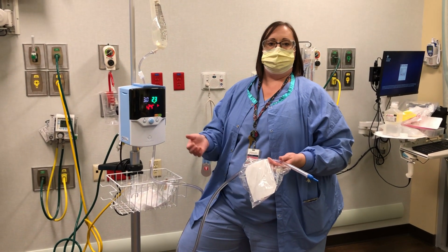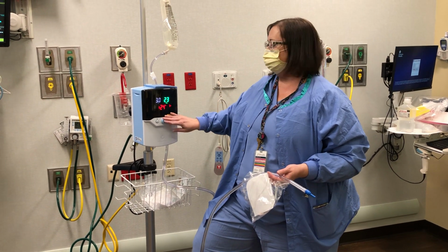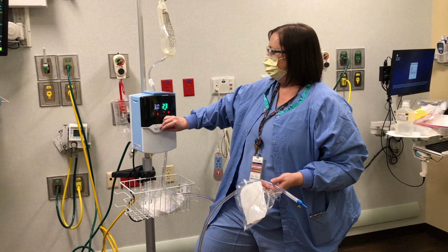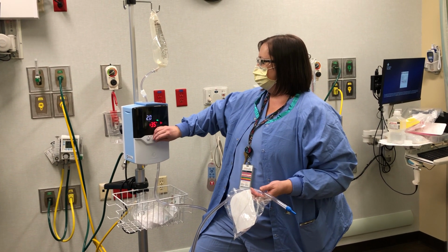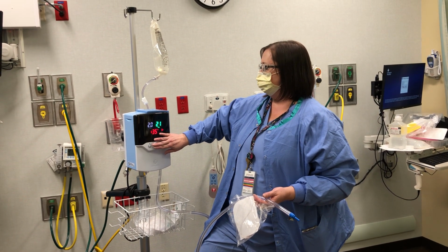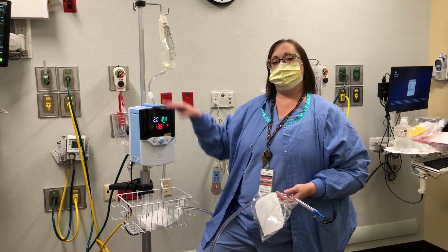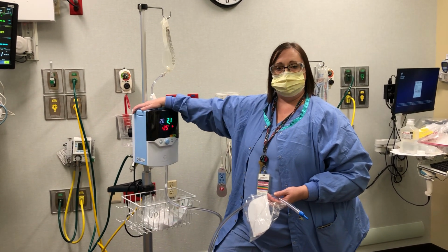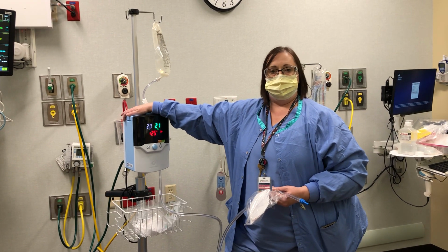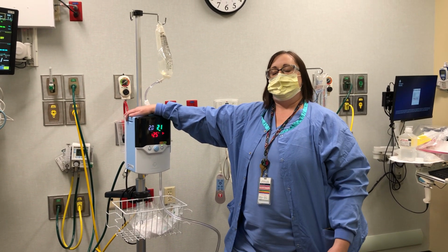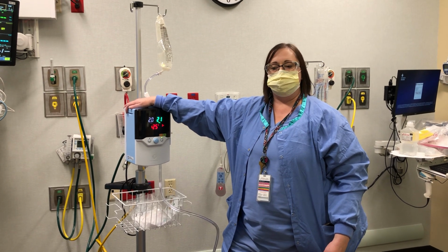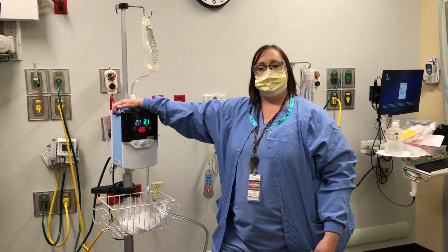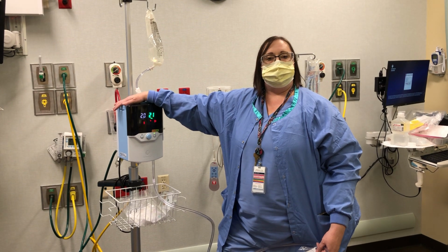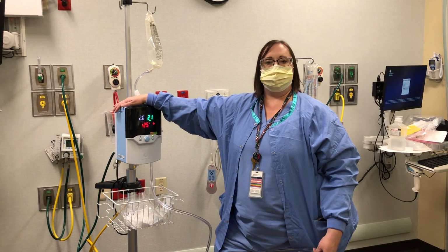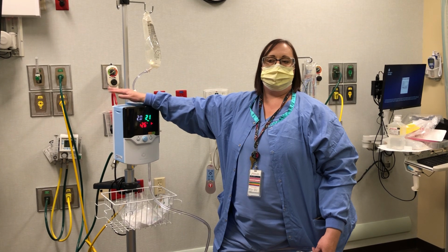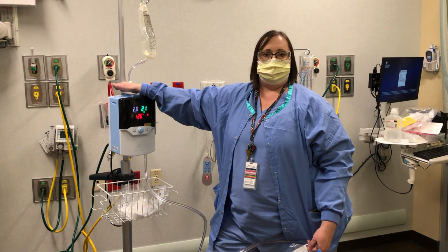And you might want to reconsider coming off of the Vapotherm. But once we get down to 2 liters, and as close to 21% as we can, then we would go to blended. We do not, even though these machines go down to 1 liter, we do not go below 2 liters on these. There are several reasons for that. One of the main reasons, however, is that our medical director had found information that the Vapotherms do not deliver an accurate flow below the 2 liters. And so to get a more accurate flow and FiO2 measurement, we switch over to the blender at this point.